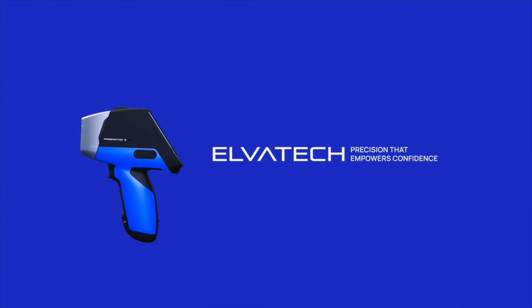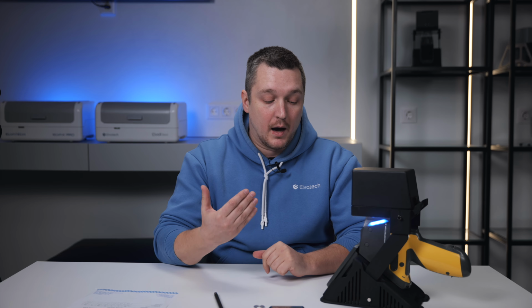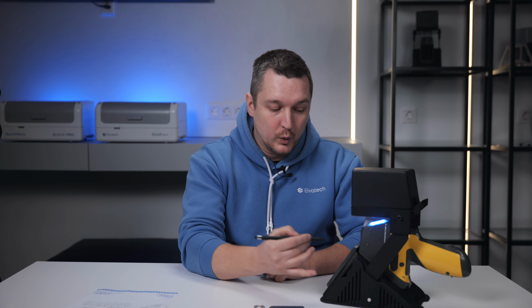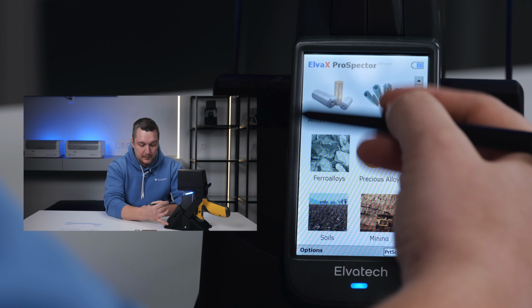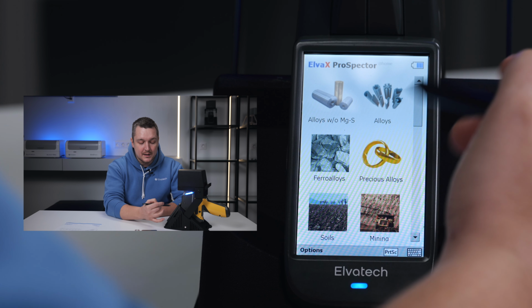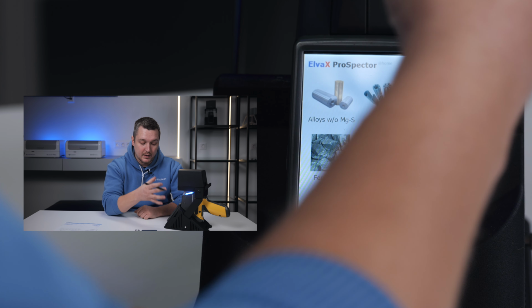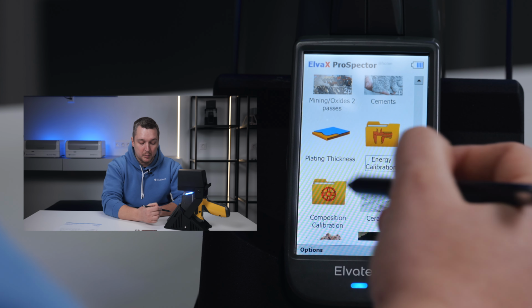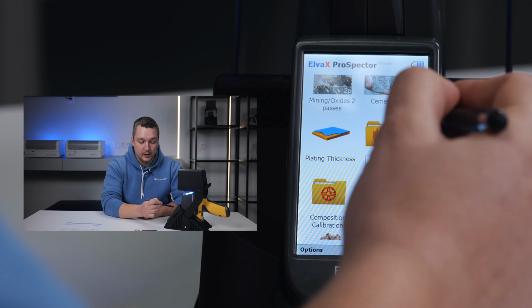Precision that empowers confidence. So, first of all, to perform the energy calibration, you need to log in to the analyzer menu with the service password. The service password you may get from our service department, and they will provide you with one and you will log in. After you log in with the service password, you will see on the main screen the calibrations that are installed in your analyzer, and also you will see several new folders like energy calibration and composition calibration. We need the energy calibration.